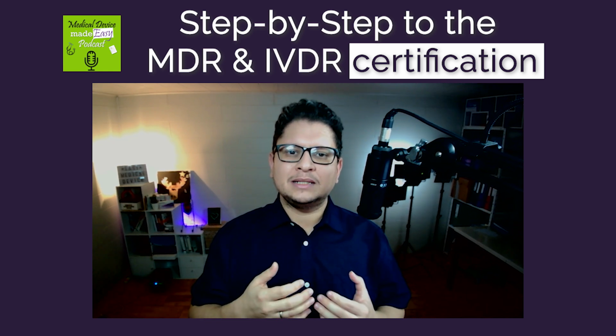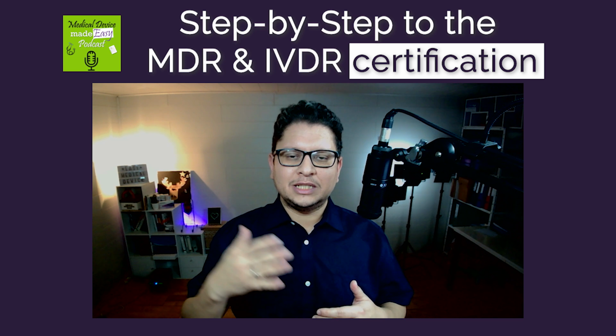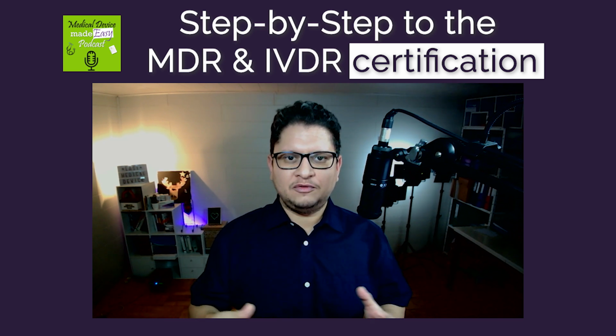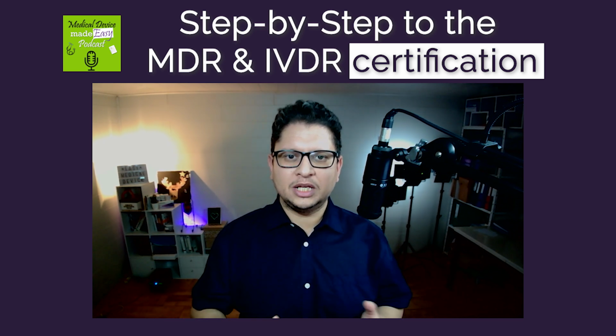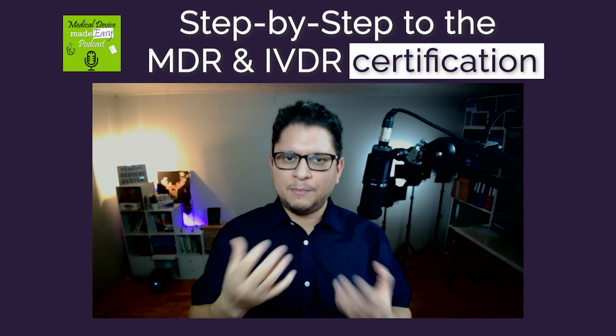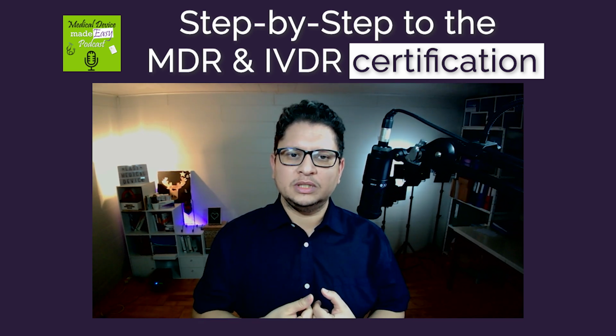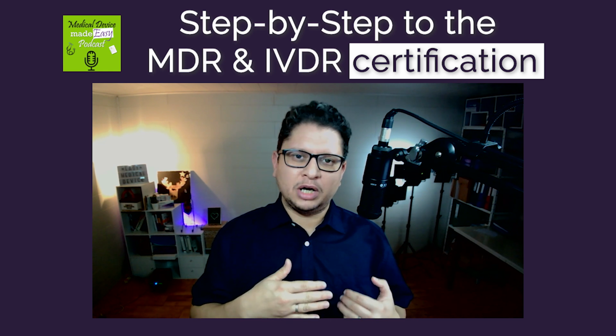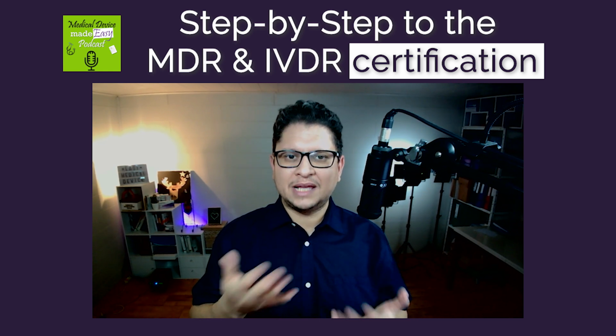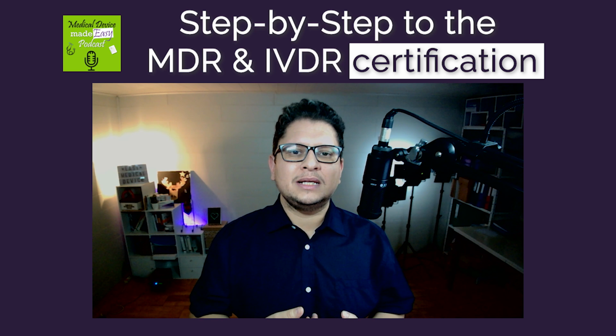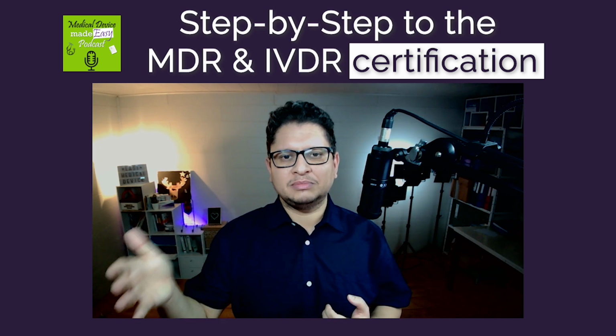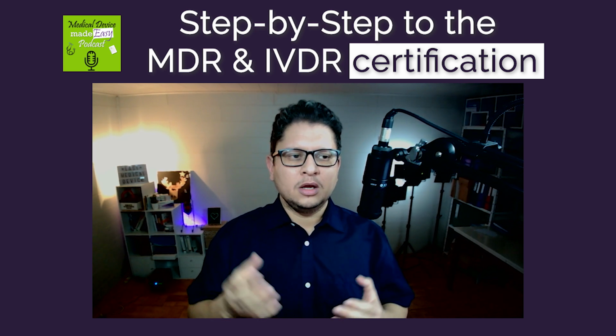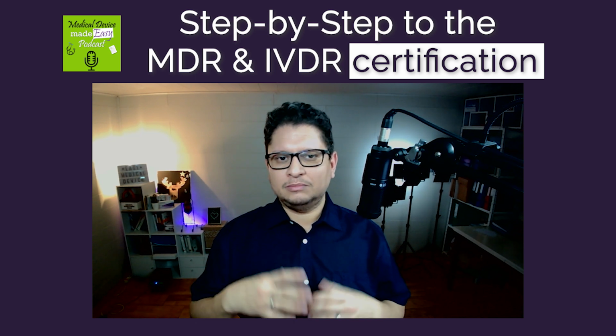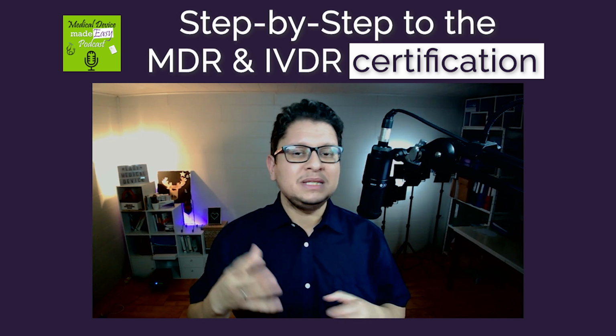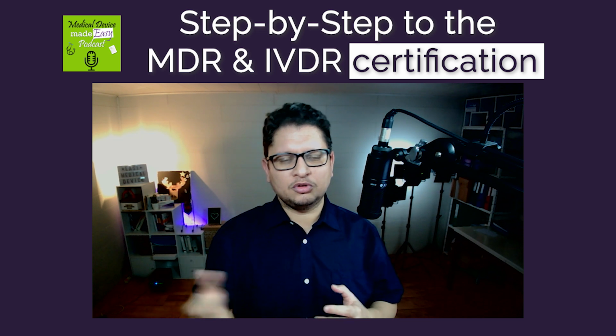What does it mean? It means that you should not wait until you finalize everything within your documentation before applying to the notified body. You should do that prior to finalizing everything, to save some time, because even when you send the information to the notified body, it can take some time, and we'll talk about that just after. Okay, you have your quality management system, everything is fine, you maybe even passed the stage 1 audit, or maybe you are in progress to do that.